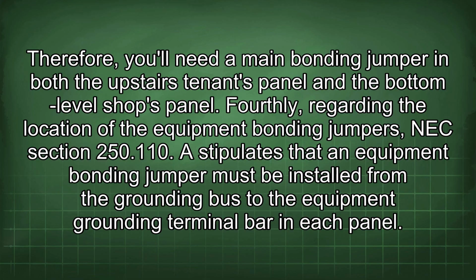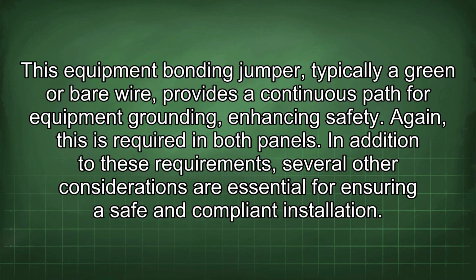Fourthly, regarding the location of the equipment bonding jumpers, NEC section 250.110 stipulates that an equipment bonding jumper must be installed from the grounding bus to the equipment grounding terminal bar in each panel. This equipment bonding jumper, typically a green or bare wire, provides a continuous path for equipment grounding, enhancing safety. Again, this is required in both panels.